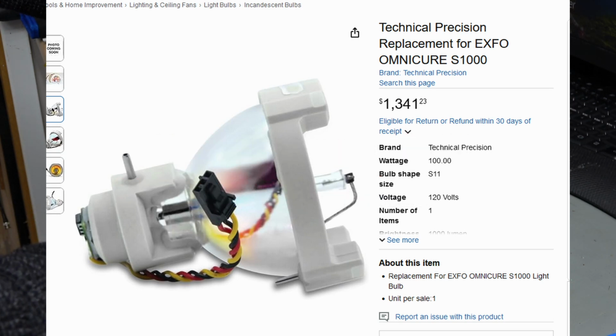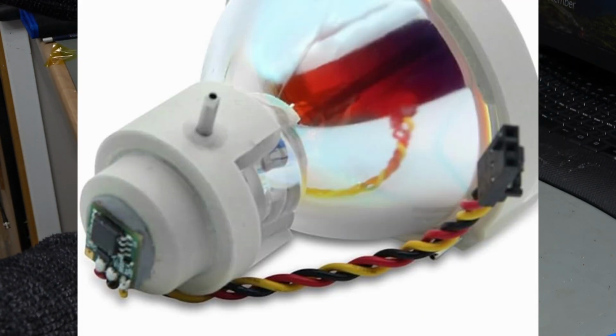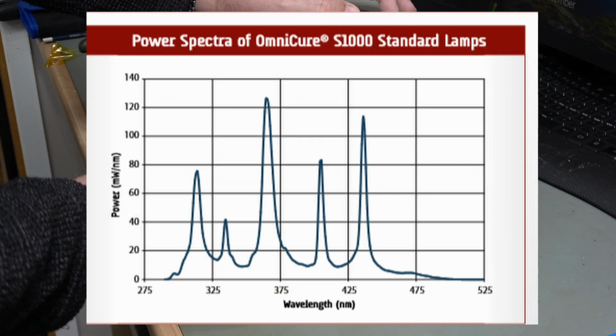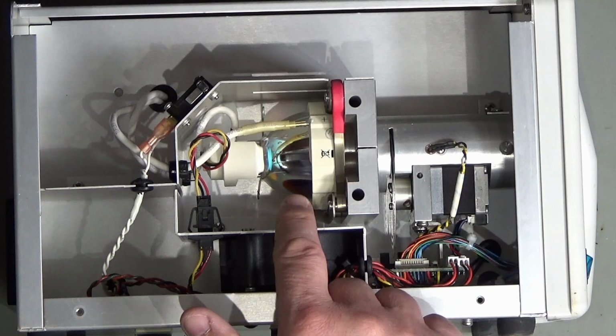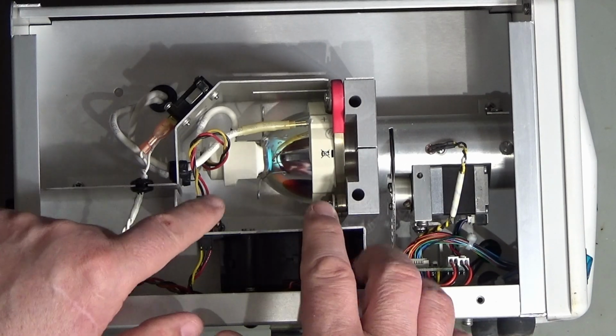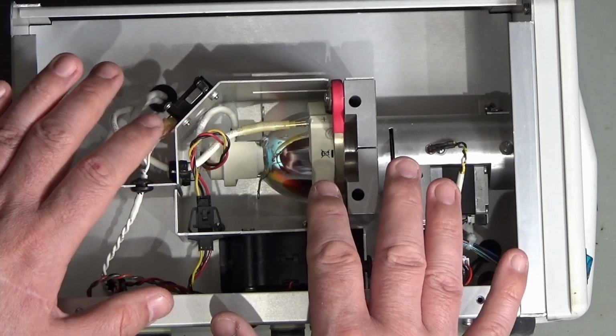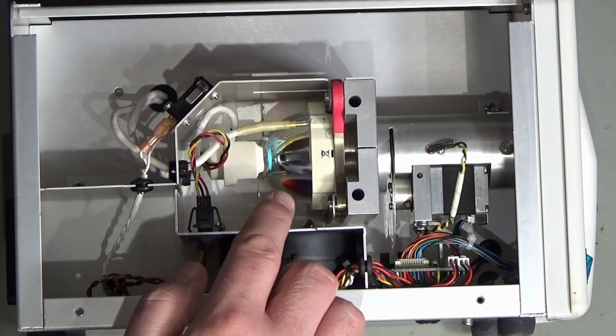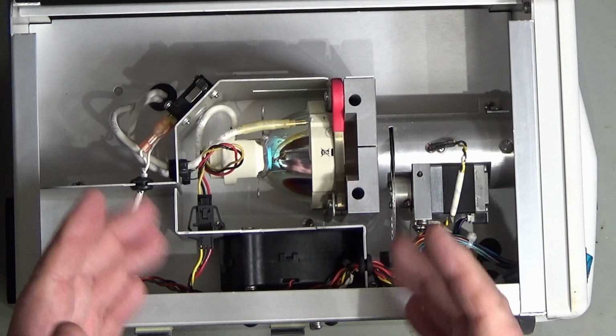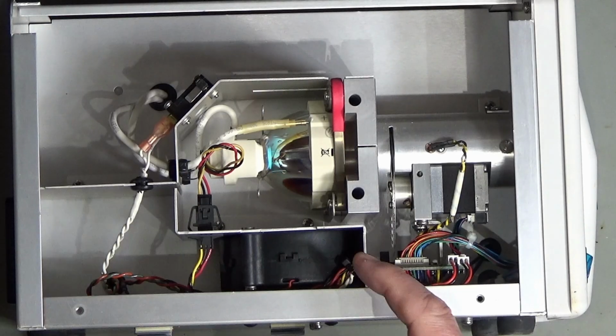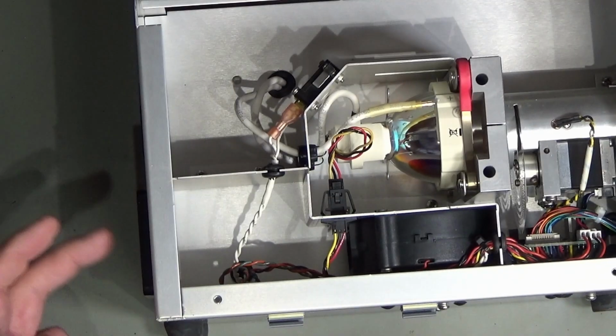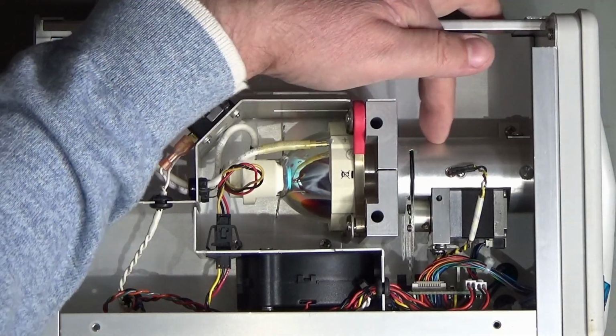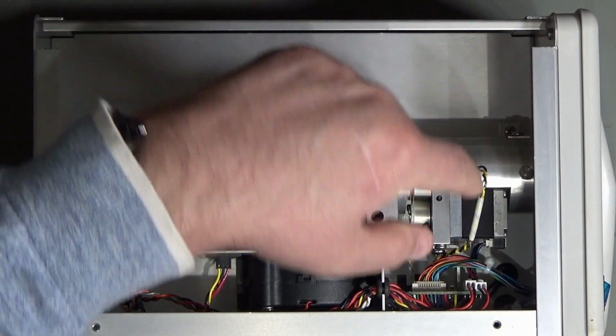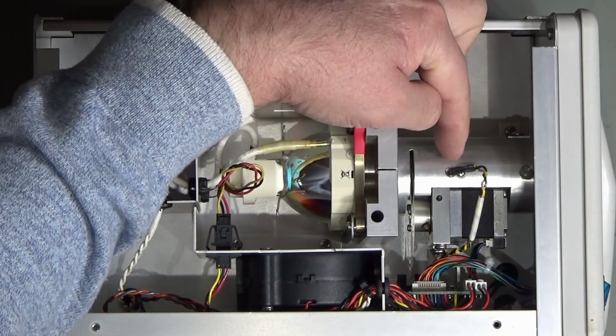The bulb is a 100-watt high-pressure mercury vapor lamp, and it's carefully pre-aligned, and it also has an integrated usage timing chip, which it reports back to the main unit. It's got a wide range of peak wavelengths, and it costs a small fortune. Fortunately, the bulb in this one has only had 500 hours of usage, meaning it has over 1,500 hours left in calibration. So that's that assembly, very straightforward, and underneath it there's a big centrifugal fan. There's a fan outlet on the back just here. You can see there's a big aluminium tube just running along here with a stepper motor bolted on the bottom, and there's a sensor here.